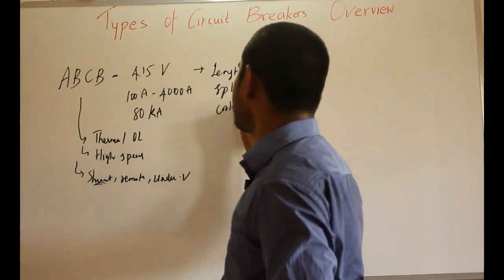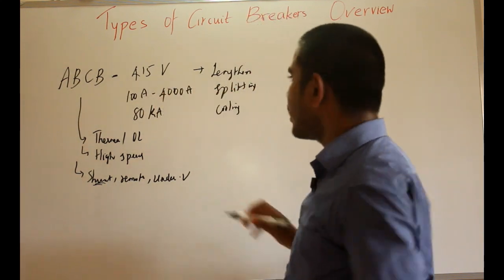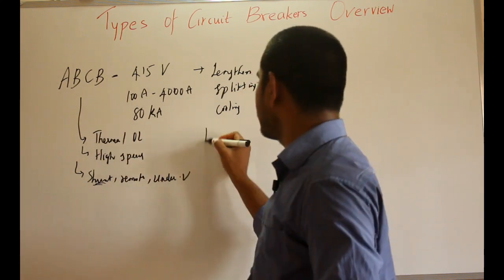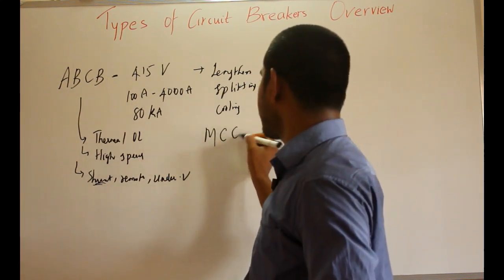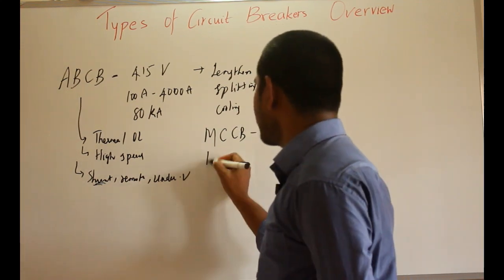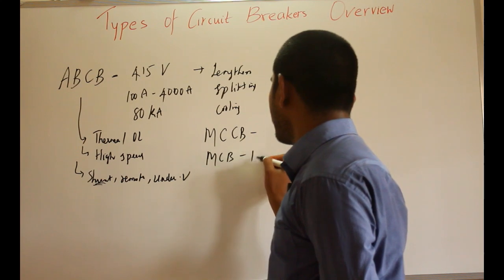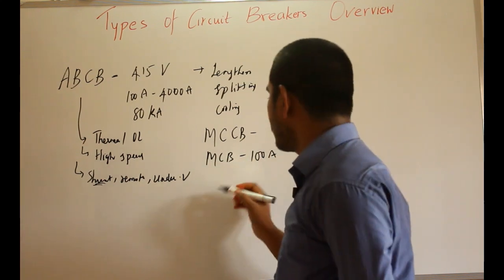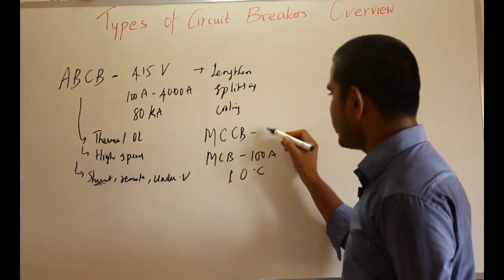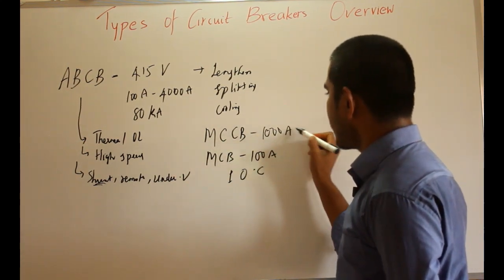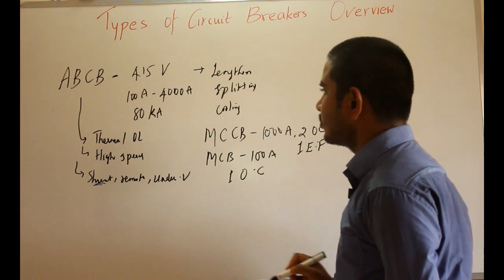Arc quenching in the air break circuit breaker can be done by lengthening the arc, splitting the arc, and cooling the arc. The latest version of the ABCB is the molded case circuit breaker (MCCB). Miniature circuit breakers (MCB) are used for up to 100 amperes with only one over-current protection, whereas MCCB is used for up to 1000 amperes and has two over-current protections and one earth fault protection.